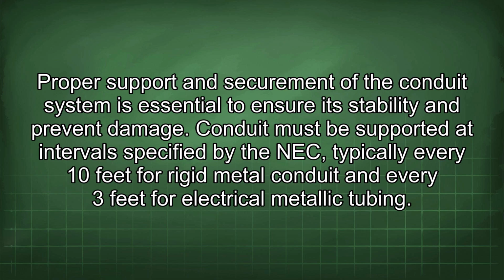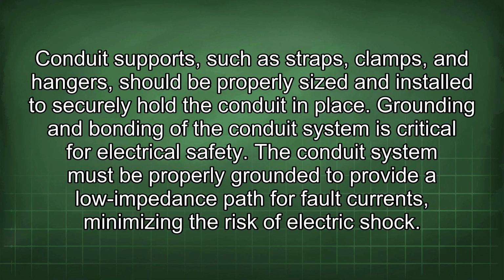Proper support and securement of the conduit system is essential to ensure its stability and prevent damage. Conduit must be supported at intervals specified by the NEC, typically every 10 feet for rigid metal conduit and every 3 feet for electrical metallic tubing. Conduit supports such as straps, clamps, and hangers should be properly sized and installed to securely hold the conduit in place.